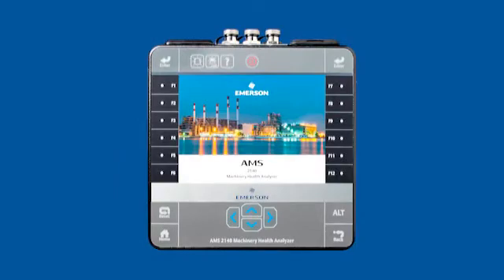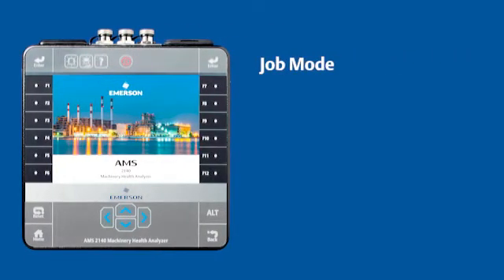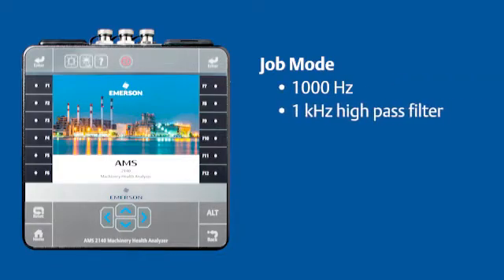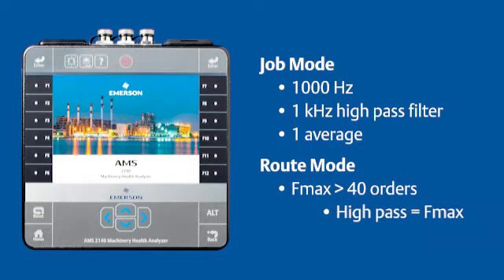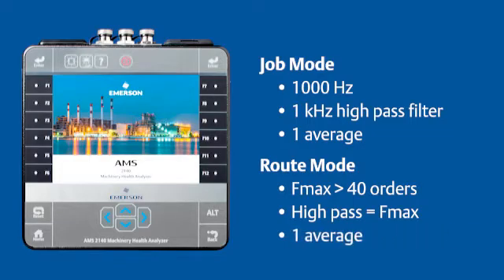Peak View measurements can be collected in both Job Mode or Route Mode. In Job Mode, the default setting will collect a spectrum up to 1000 Hz with a high-pass filter of 1000 Hz and one average. If you are in Route Mode, the settings will depend on the measurement point definitions. A good general recommendation would be to use an FMax with at least 40 orders and a high-pass filter that is equal to the FMax. It is important that when collecting Peak View data, you only collect one average.